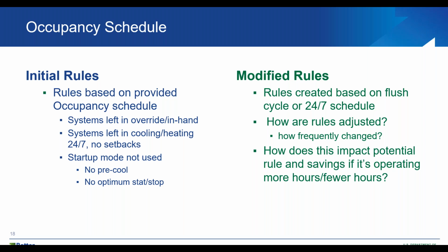The next area would be occupancy schedule. Under initial rules, you have rules that are developed based on people occupancy, HVAC occupancy. Again, if people are coming in 8 to 5 or 8 to 6 during the weekday, expect the systems to be operating a little before that and a little after that. And they might also have a pre-cooling mode in the Northeast, at least, to pre-cool the space during the summertime, as well as optimum start and stop. So they're preset rules that are developed based on the current occupancy schedule.